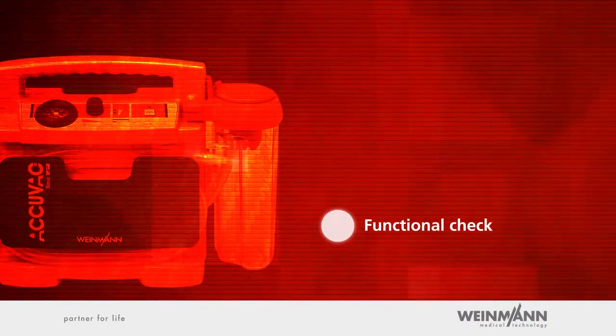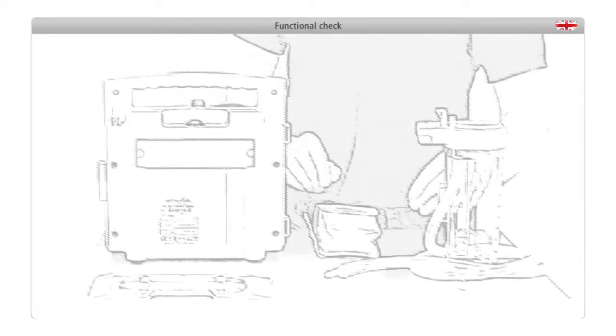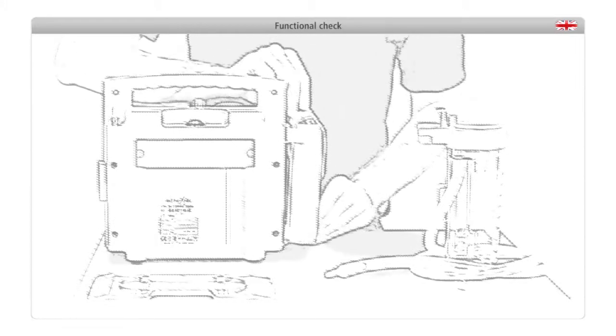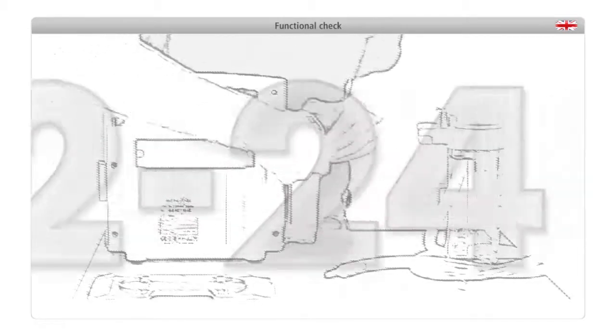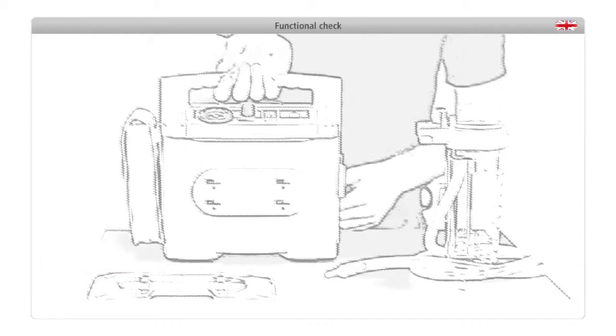Functional check. To ensure that Accuvac Basic is ready for immediate use, carry out a functional check: one, before every use, for instance at the start of every morning shift; two, after every disassembly for hygienic conditioning; and three, at least every six months.